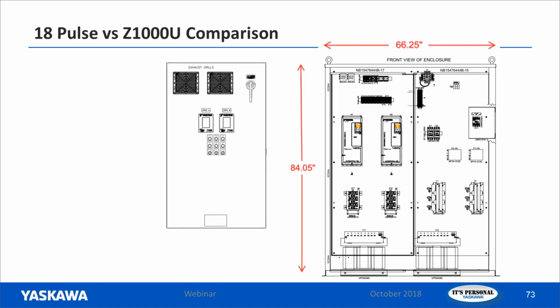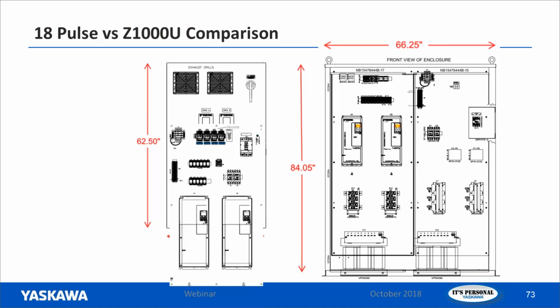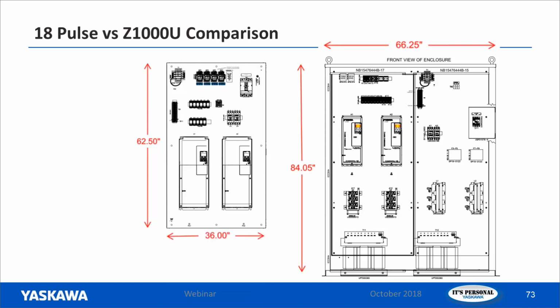There it is. Here we have on the left Z1000U redundant package, the 50 horse redundant package for a 4-motor array. And in case you don't believe me, we'll take a look inside here in a minute. This is 62½ inches high, 36 inches wide, and it is a wall mount enclosure. This is a real world example. This exists. We built this. So here it is, 50 horse redundant Z1000U drive, and we've got our 4-motor array built in here. So this package on the left, once again, is doing everything the package on the right is doing, but it's doing it better, and it's doing it for less money.